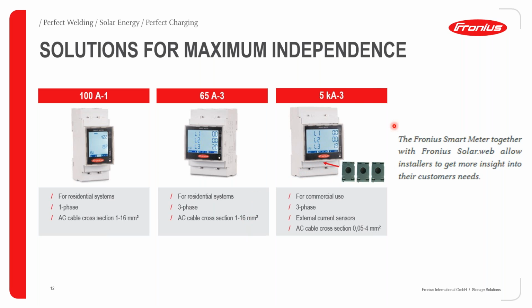We also have the big 3-phase smart meter, which is the 5 kiloamp smart meter. With the smart meter, you have to use external CTs, and you can use any external CT as long as they have a secondary current of 5 amps.